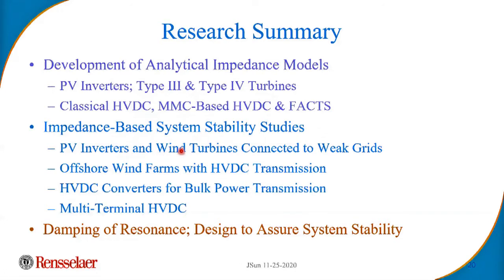Typically the practical problems that people experience are related to the so-called weak grid. You have larger scale wind and PV with long transmission lines, and that's a recipe for a lot of problems. Offshore wind is a special case of that weak grid. Then there is HVDC transmission and multi-terminal HVDC, which you've heard about in Europe and China. We had a couple of projects on those. This has to do mostly with understanding the system behavior, identifying common modes of instability, and then proposing technologies and designs that can mitigate those things, providing experience to the industry.